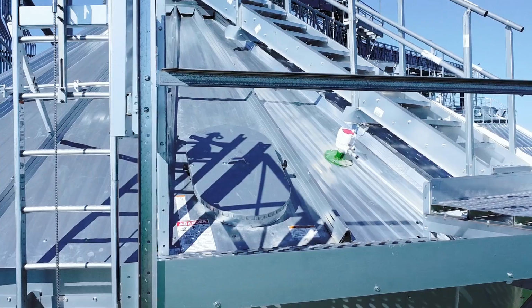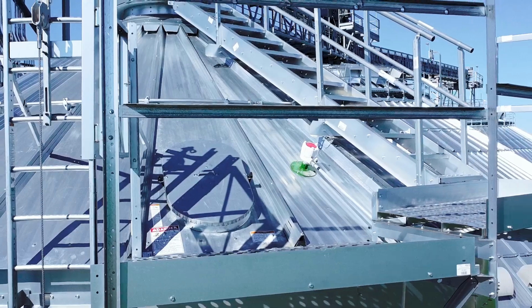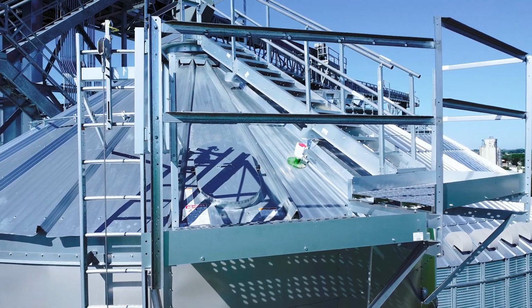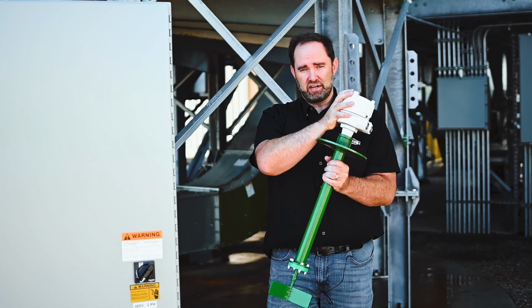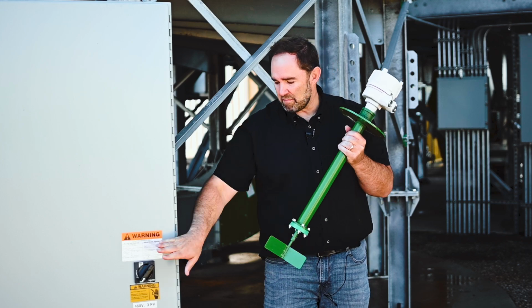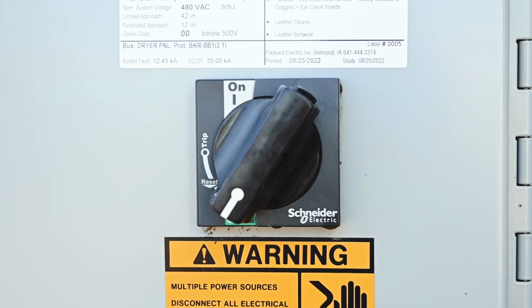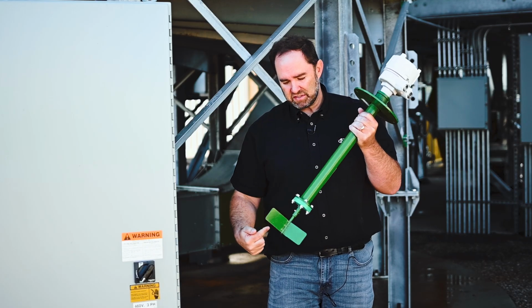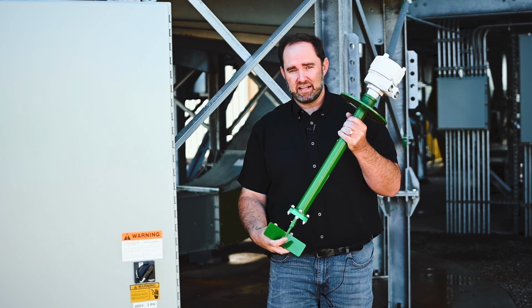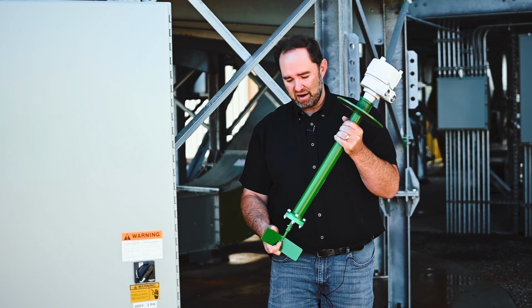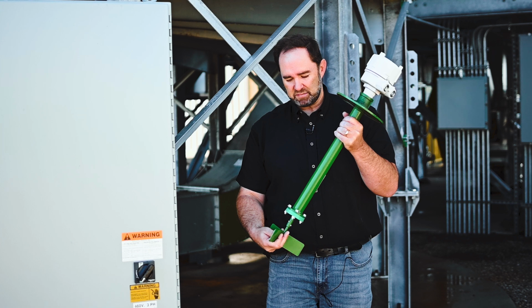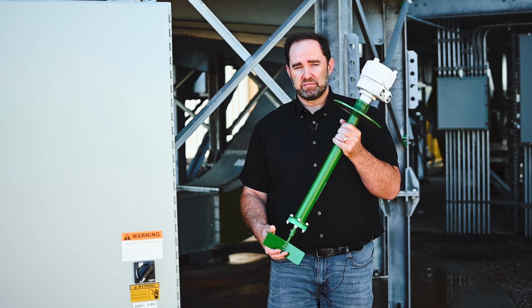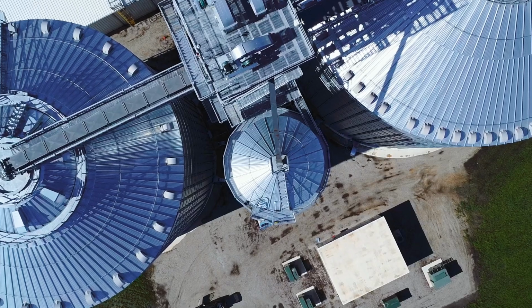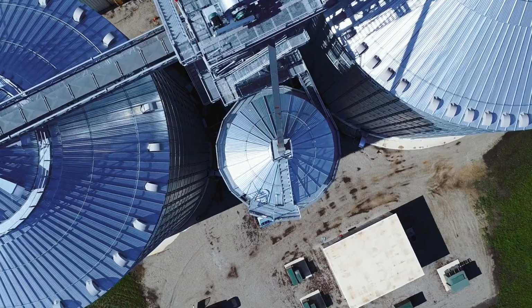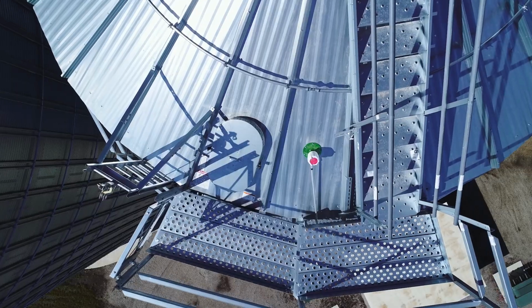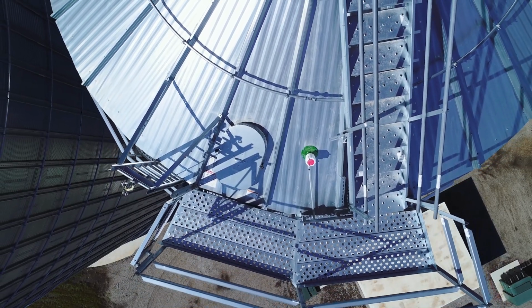Okay, this is the fill switch that's up on the roof of the tower dryer. So it would be mounted like this on the roof. Rotary fill switch here, or just a rotary switch here. This is always turning. So whenever the main power is on, we have 28 volts being generated. This rotor is always going to be turning down inside, below the roof of the dryer. And when grain comes up to it, it gets to this paddle and it stops it from turning. And that's what tells the PLC that it is full of grain. So when the grain level comes down, it goes away and this starts turning again. That tells the dryer we need grain, and it turns on the fill system of the dryer.